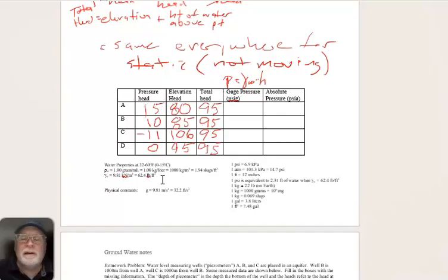We like to do things in PSI, pounds per square inch. So 12 inches per foot would be 144 square inches per square foot. Converting that to PSI, you'd have 62.4 times H divided by 144. So you get 0.433, or another common number you might have in your head is 2.31 feet of water per PSI.